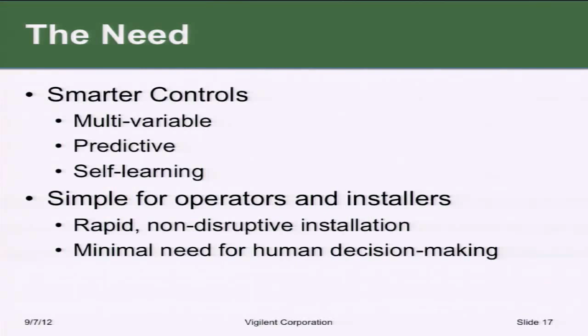I haven't touched on this need quite as much, but the fact is that in a data center, the IT equipment, the servers, has an equipment life of about 3 years, while the cooling equipment has a life of about 15 years. So that means 5 equipment refreshes on the IT side for every 1 refresh on the cooling side. That means stuff is constantly coming and going, the racks come and go.